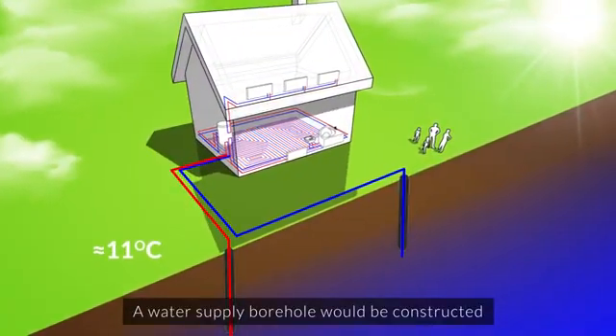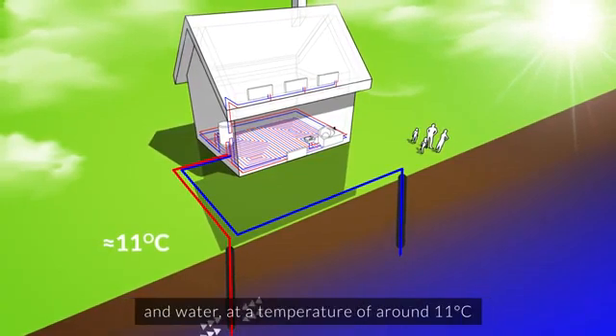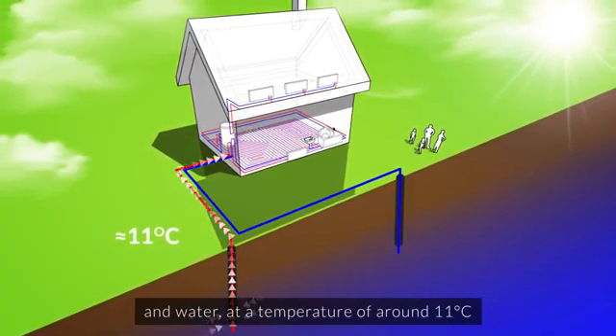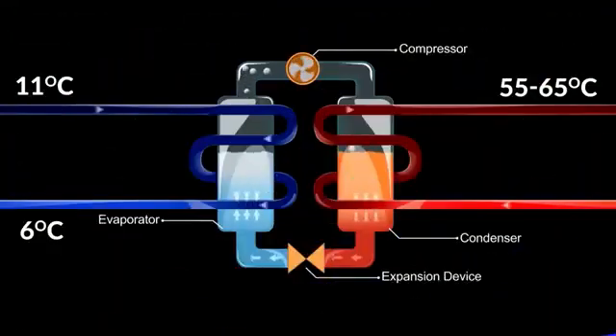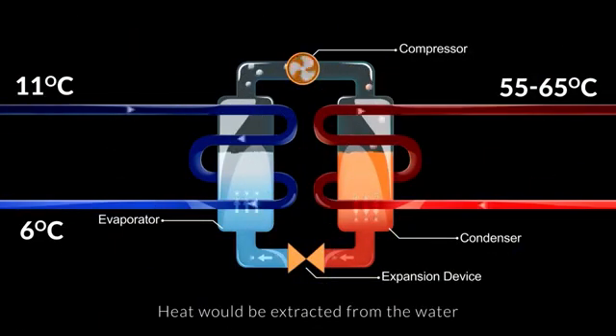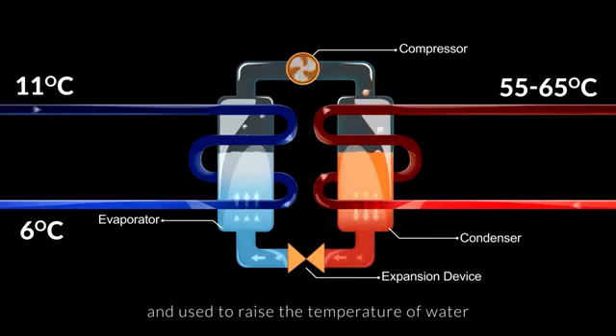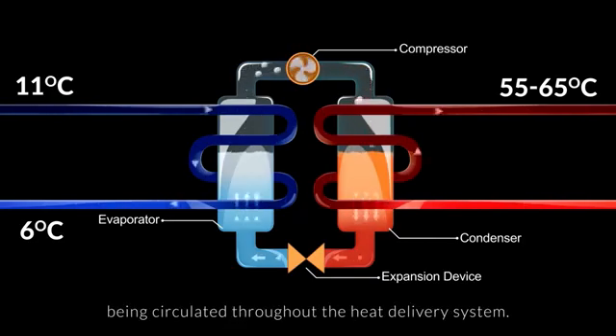A water supply borehole would be constructed, and water at a temperature of around 11 degrees Celsius is pumped into the building to feed the heat pump. Heat would be extracted from the water and used to raise the temperature of water being circulated throughout the heat delivery system.